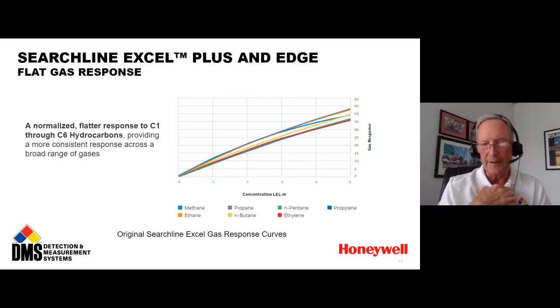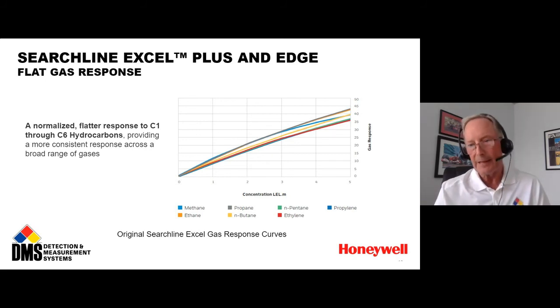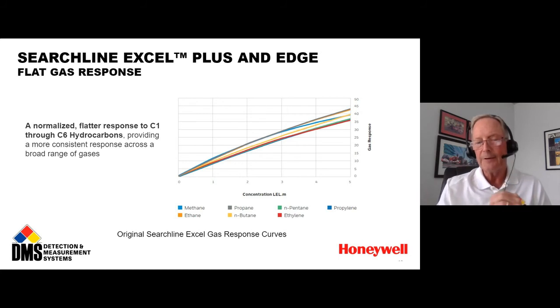And what I'm excited about is that historically we've not been able to stock Searchline Excels here at DMS, because we keep $300,000 worth of Honeywell Analytics inventory here at our offices because we like to have inventory available for our customers. But we weren't able to stock Searchline Excels because of that broad spread of relative responses for all those gases, and the fact that you had to pick the right calibration, and we can't change the calibrations on this end. So it just made it too difficult for us to stock. But with this new detector and the tight cluster of responses, we're going to look very seriously at putting some of these on the shelf so that we have these available for rapid delivery to our customers. So this is quite a big change in the new product from Honeywell.